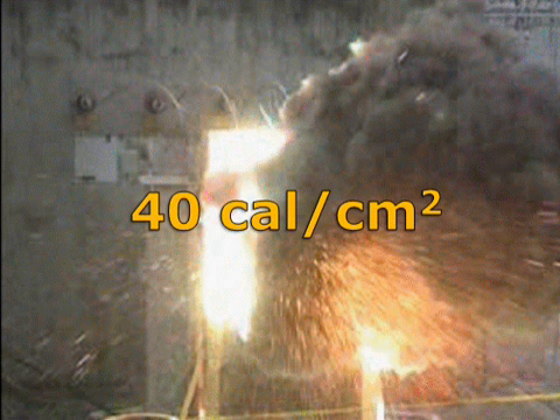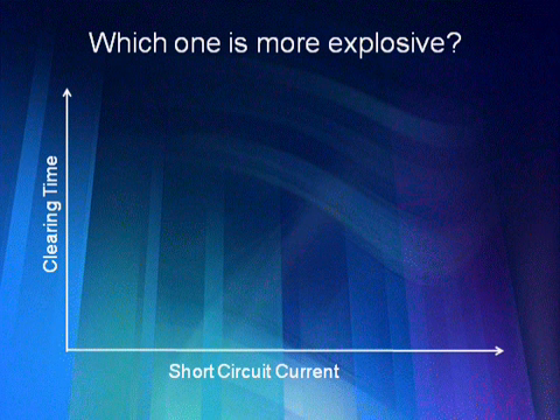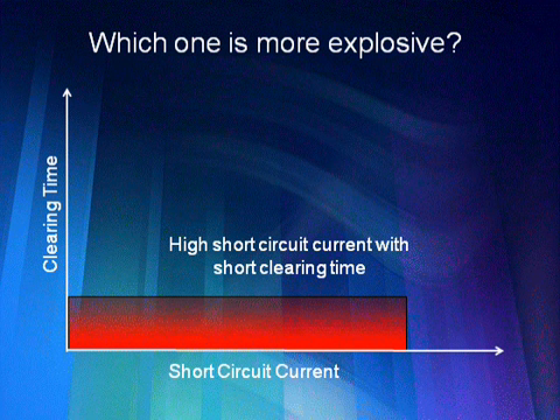So hopefully that question will be answered. Another question area is the 40 calorie per square centimeter limit. This is referenced frequently, and in fact I just had an article out in Electrical Contractor magazine about 40 calories. And more investigation needs to happen, because the problem with the 40 calorie limit, if you have a large magnitude short circuit current over a short duration, yeah, that's going to be explosive.